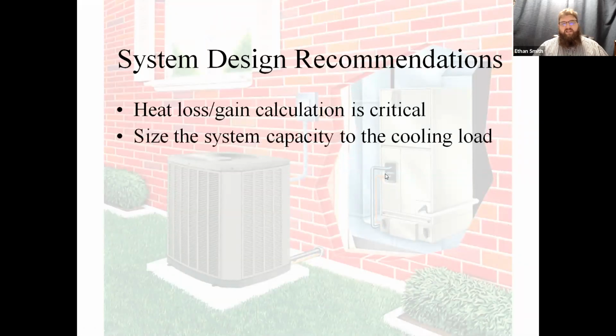You've got to size the system capacity typically to the cooling load was the rule of thumb. Now with the advent of variable speed outdoor units, a lot of times we get better heating BTU output out of them than cooling BTU output. And so we're actually going to size them to the heat pump in the heating capacity of the unit, depending on which style unit you have. So you have to be aware of which equipment you're going to use. If it's going to be a frequency driven compressor, you're going to size it one way. If it's going to be a standard system, you're going to size it in another way. So be aware of the equipment you're going to use.